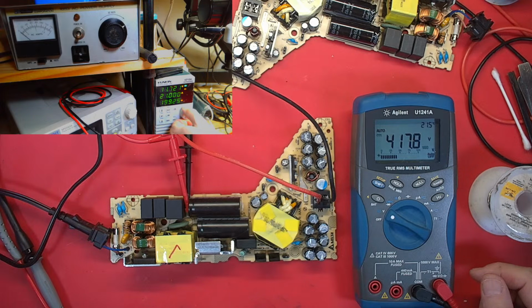17, 18. Oh, I can't count apparently. I'm turning and just counting and not really looking at the dial. That's 21 amps right there. 22, 23, 24, that's 25. It seems like it's jumping here. 26, 27, 28, 29, 30, 31. Yeah, 31, it likes to jump up to 417 volts.